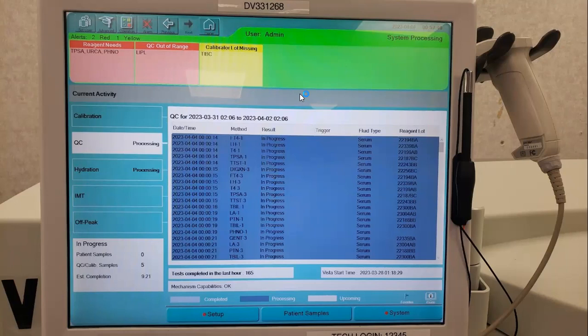This is easier to do than going one at a time because there's a lot of levels that we have, and you want to make sure that you're documenting correctly what you're doing to try and get the QC back in range. So after 10 minutes, we'll come back and put on all the reagent. Well, we'll put the reagent needs on immediately, and then we'll wait the 10 minutes for the rest of the QC levels to be ran to see if this is the only level that we need to worry about today.